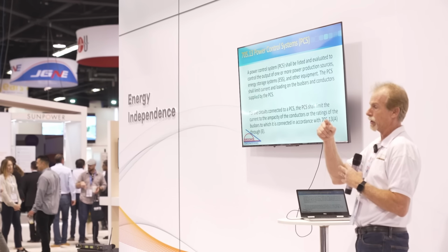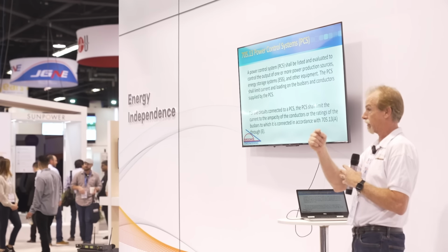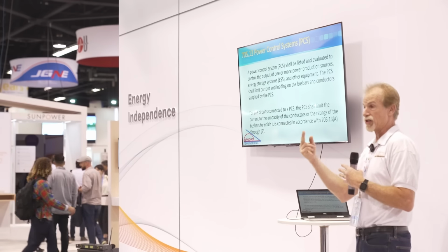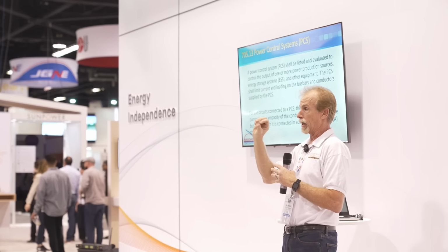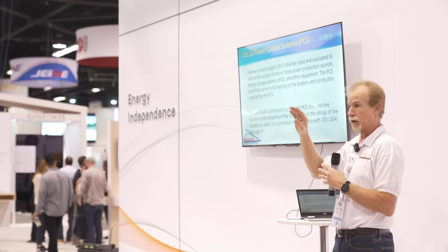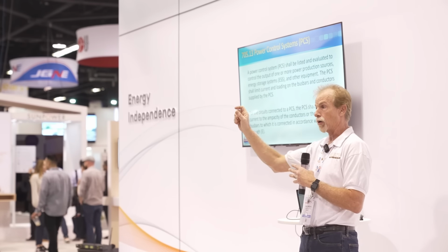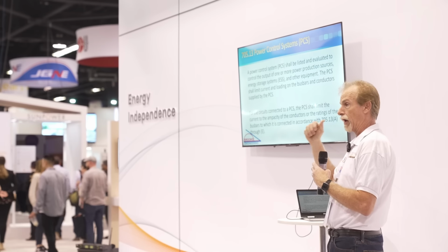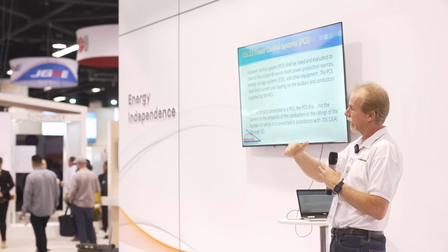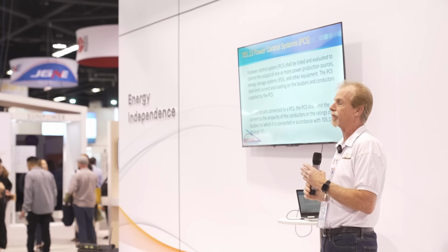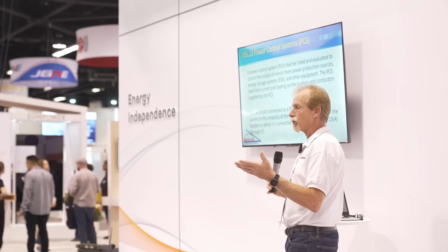unless that charger is part of a system that is monitoring the service conductors and can either, a very simple one, in fact I think Savant's a company that does this, they can turn off an EV charger directly or ramp it down, or in the case of Franklin, they have a smart circuit, and so if you put your EV charger on the smart circuit, it gets over a certain point, you just cut it off. That's kind of the brute force method.